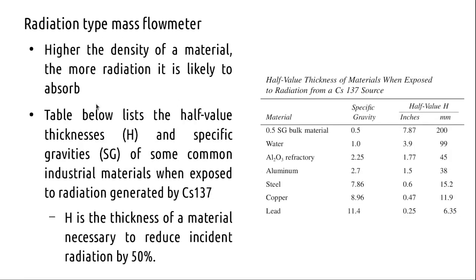To measure density using radioactive sources: if a liquid flowing through a pipe is more dense, it will absorb more radiation. From the reference table, lead absorbs the most radiation — requiring the least thickness to stop gamma rays — compared to bulk materials with specific gravity of 0.5 or even water. This absorption principle, based on Cesium-137, can be applied in chemical plants, breweries, and food processing industries.